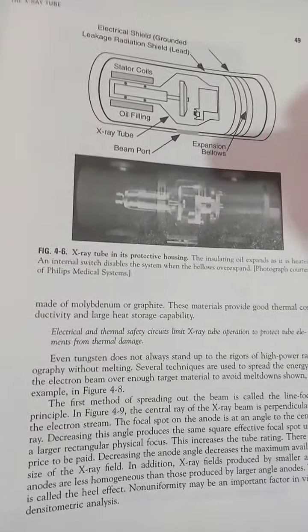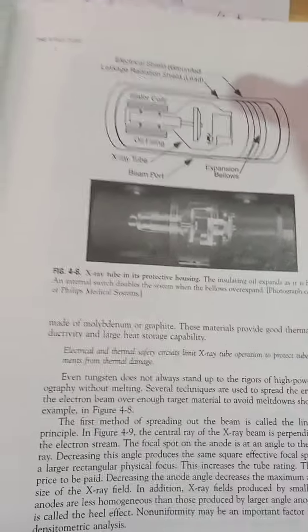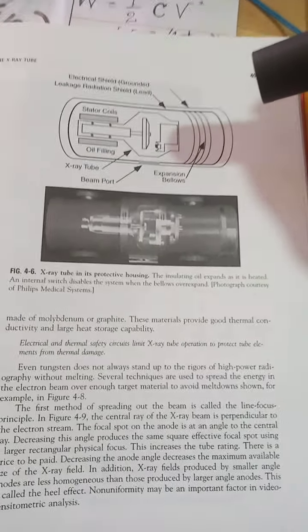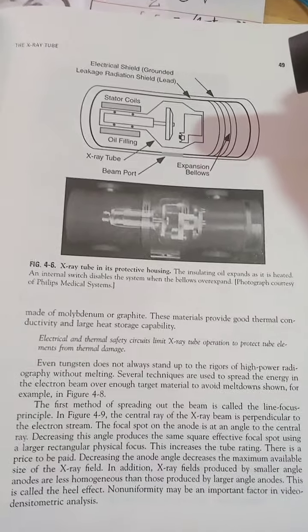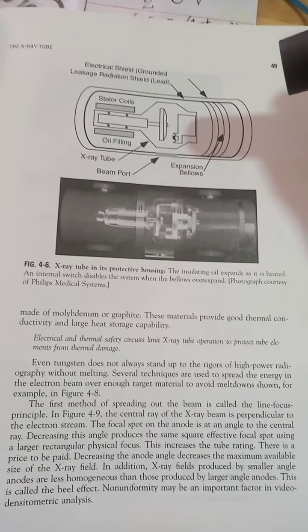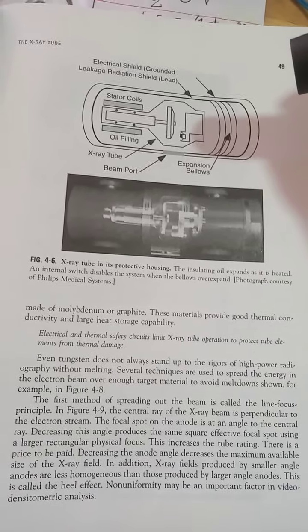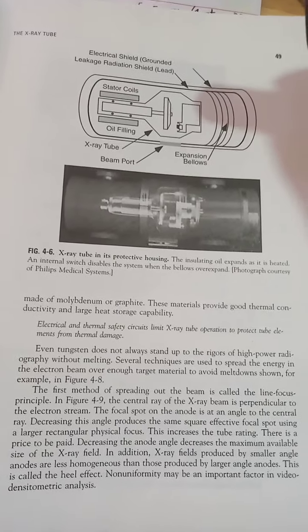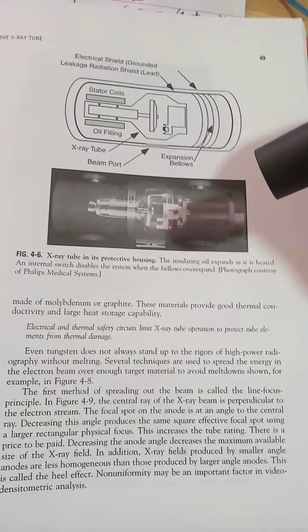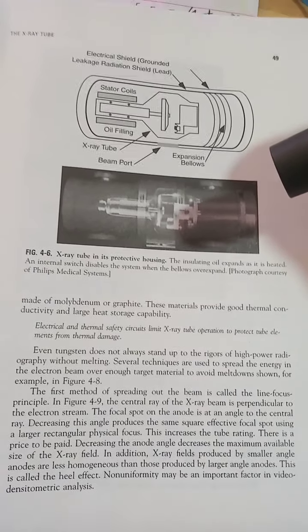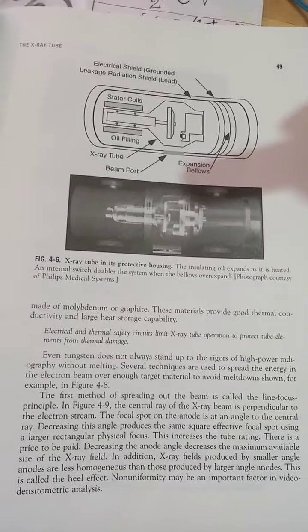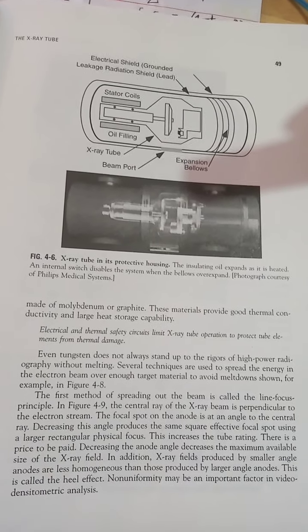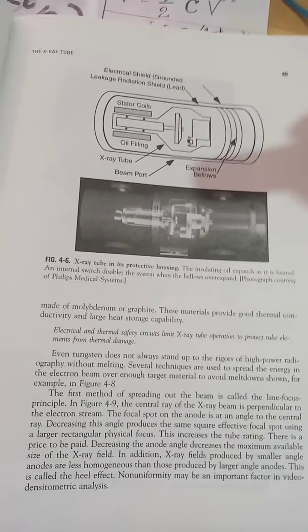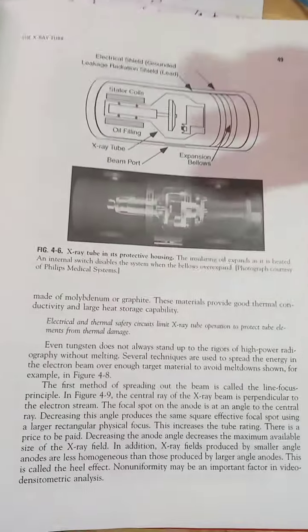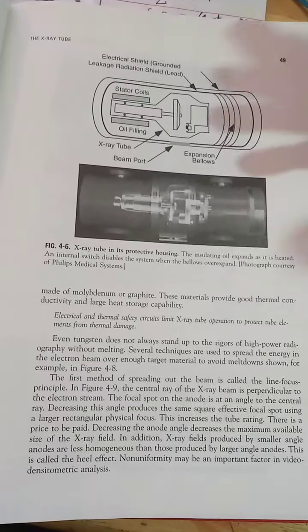The body of the anode is often made of molybdenum or graphite, as I mentioned earlier, and these materials provide good thermal conductivity and a large heat storage capability. Electrical and thermal safety circuits limit X-ray tube operation to protect tube elements from thermal damage. Even tungsten doesn't always stand up to the rigors of high-power radiography without melting. Several techniques are used to spread the energy in the electron beam over enough target material to avoid meltdowns, shown, for example, in figure 4.8 over the next page. I don't know why this book can't keep figures and the text on the same page.